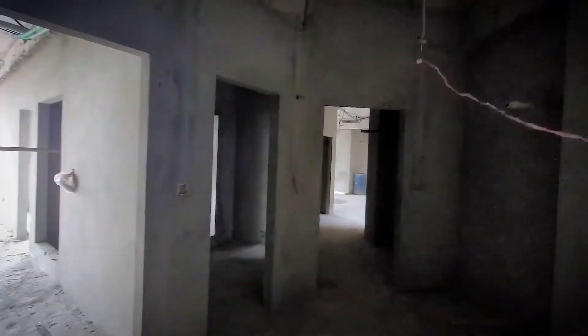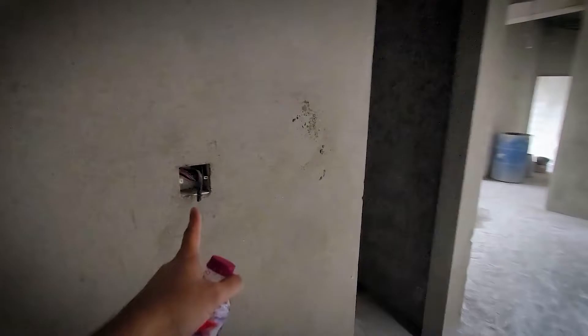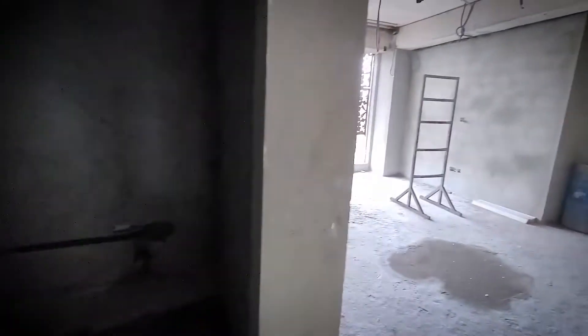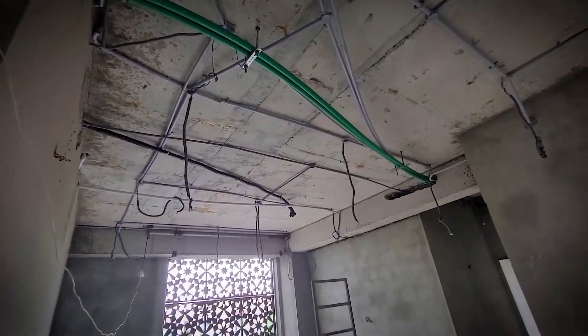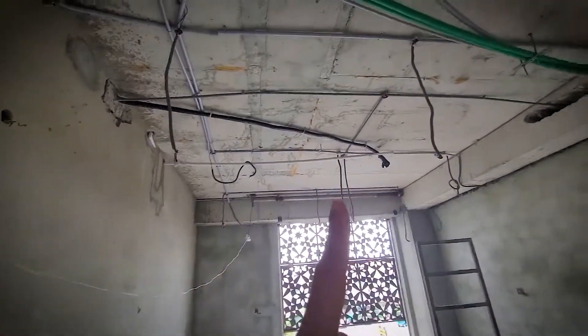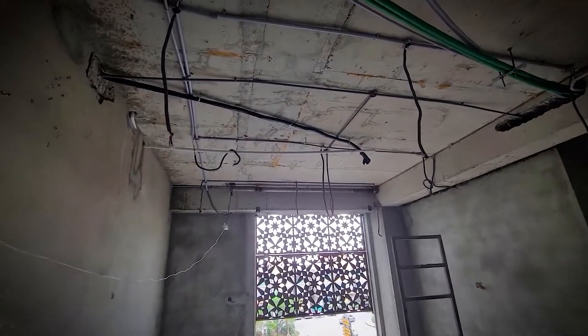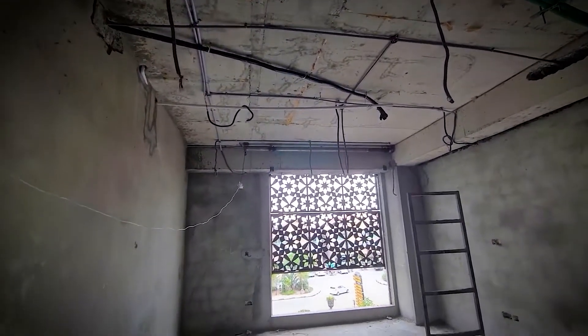Going into one of the apartments — this is the fire alarm system. All the lighting is fully complete, including the cabling, and the PPR plumbing is fully complete and fully tested. This is where most critical works get eventually hidden behind the ceilings. You can see the pipe for the air conditioning — this is a Type C three-bedroom apartment with a cassette type air conditioning unit in the center, so piping for that is complete. Water work is complete, electricity work is complete.